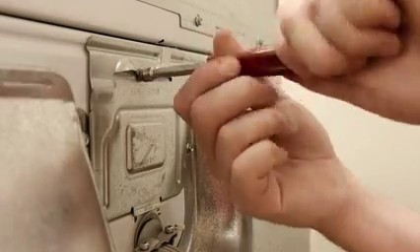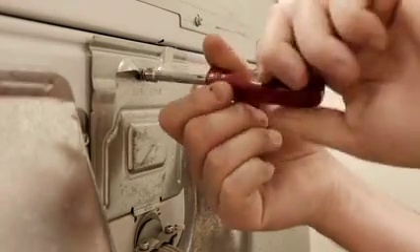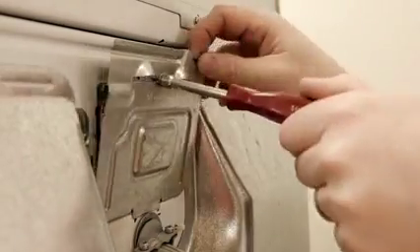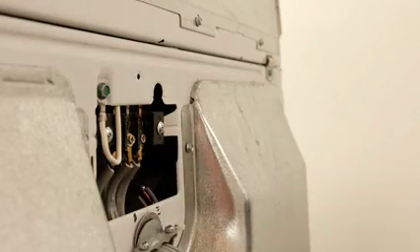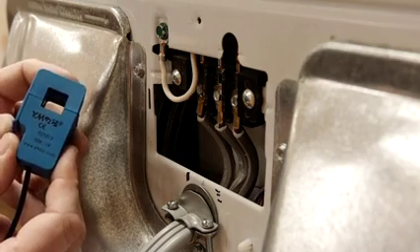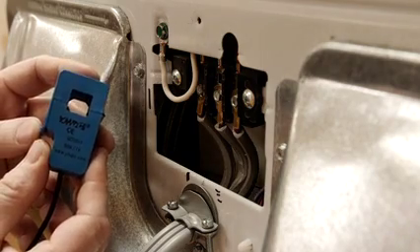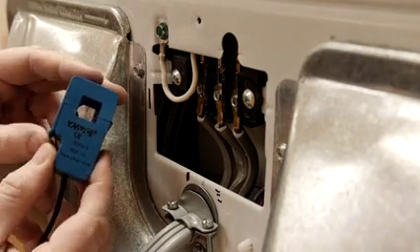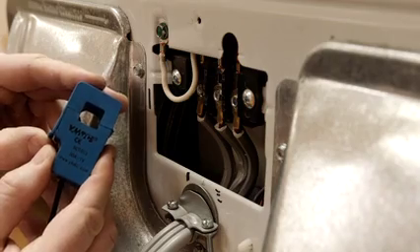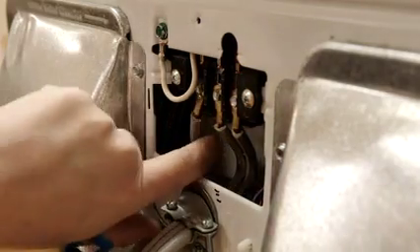Finally, to install the current sensor, disconnect all power from the dryer and locate the power wiring compartment. The current sensor must be clipped onto a hot conductor from the clothes dryer's power cord to properly interlock the ventilator to the clothes dryer.